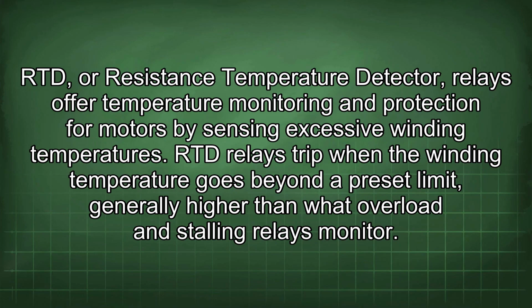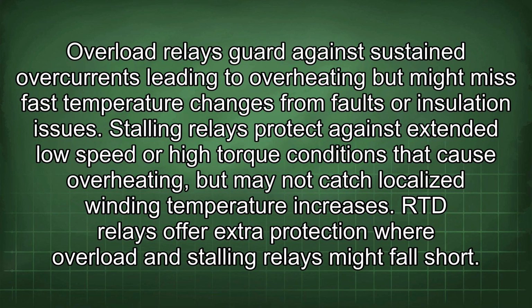RTD, or Resistance Temperature Detector, relays offer temperature monitoring and protection for motors by sensing excessive winding temperatures. RTD relays trip when the winding temperature goes beyond a preset limit, generally higher than what overload and stalling relays monitor. Overload relays guard against sustained overcurrents leading to overheating but might miss fast temperature changes from faults or insulation issues. Stalling relays protect against extended low speed or high torque conditions that cause overheating but may not catch localized winding temperature increases. RTD relays offer extra protection where overload and stalling relays might fall short.